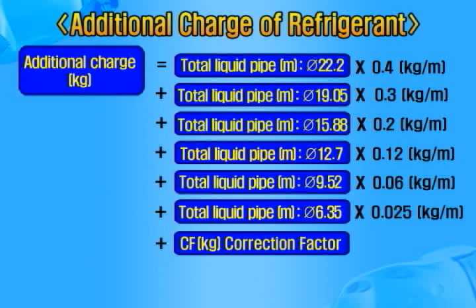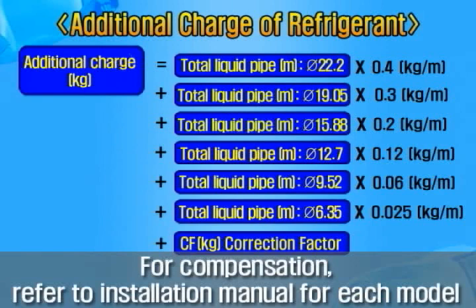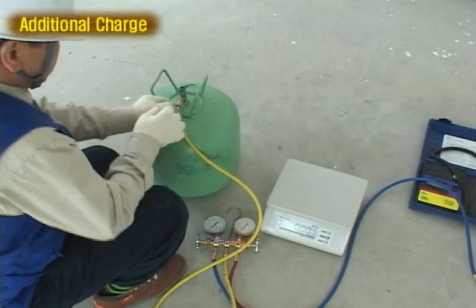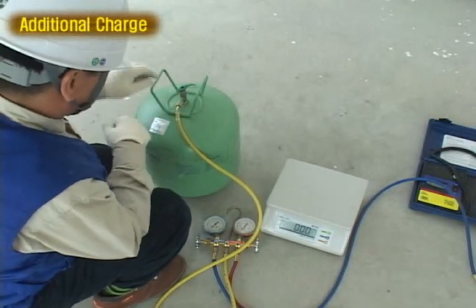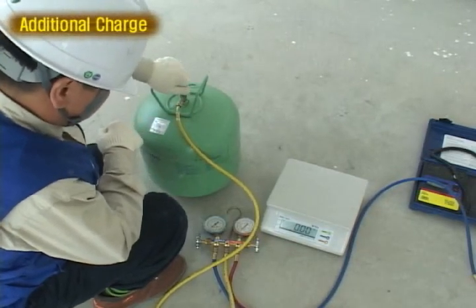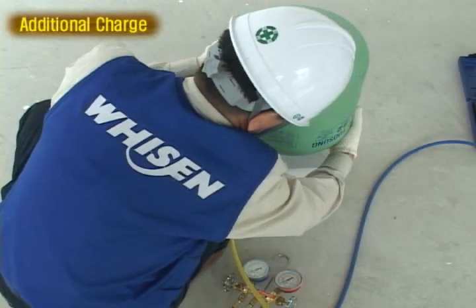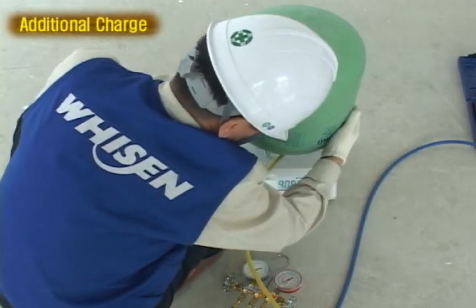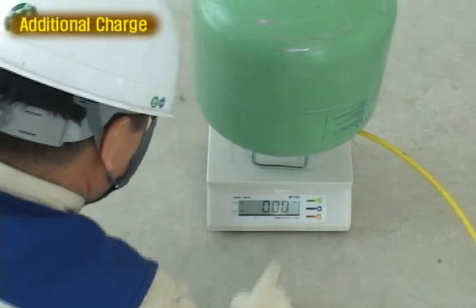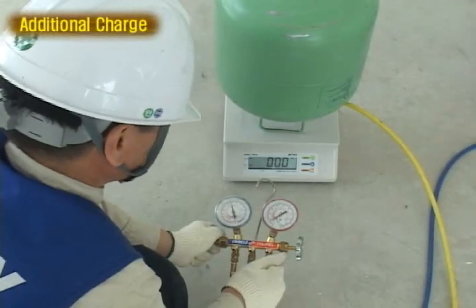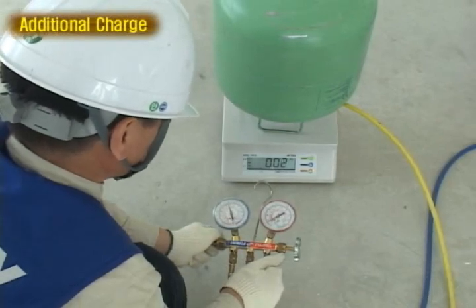In case of the long pipe installation, additional refrigerant is to be charged. Calculate the needed amount of refrigerant according to the liquid pipe diameter and additional length. Connect the middle hose of manifold gauge to the gas bulb and open its valve. Purge out the air in the hose and put the bulb on the digital balance. Set the balance value to 0 and open the valve to charge. Close it when the calculated amount is charged.